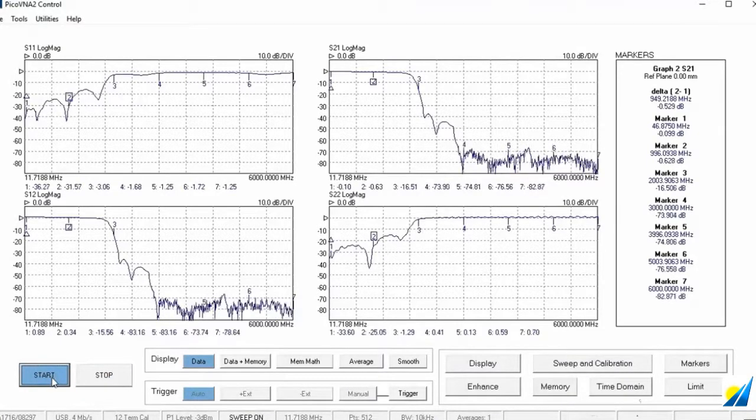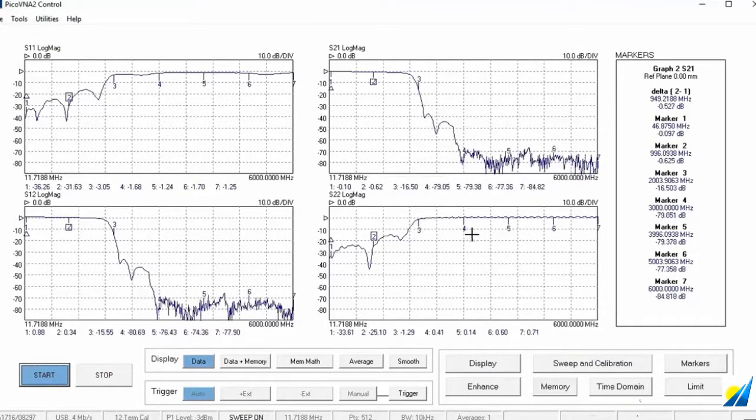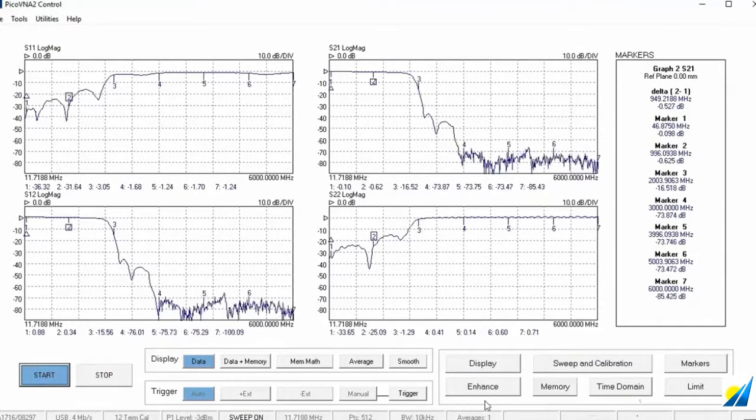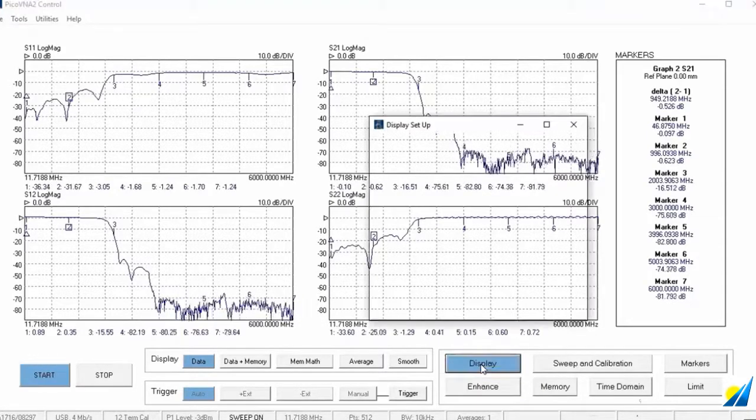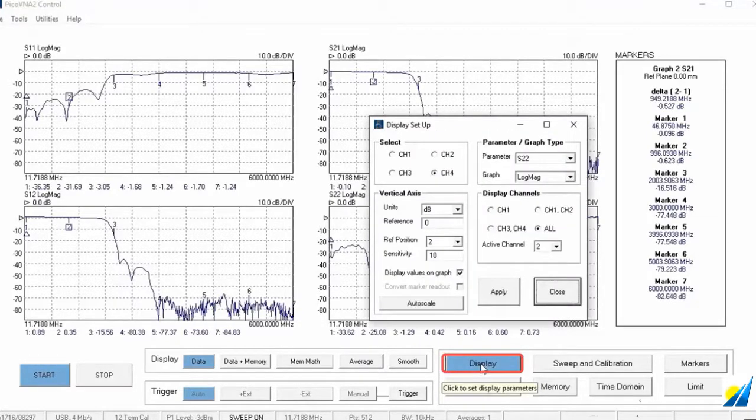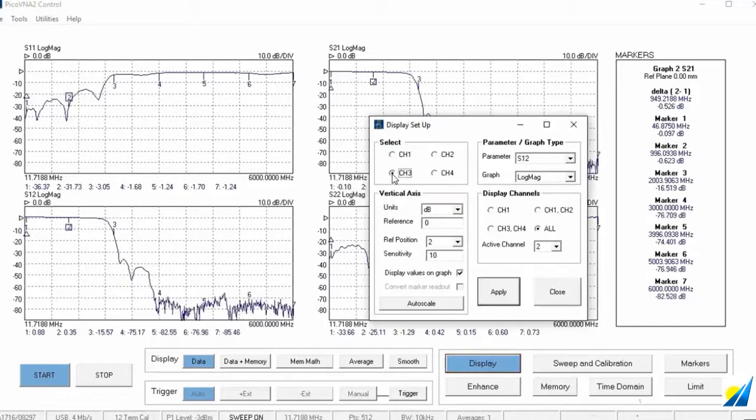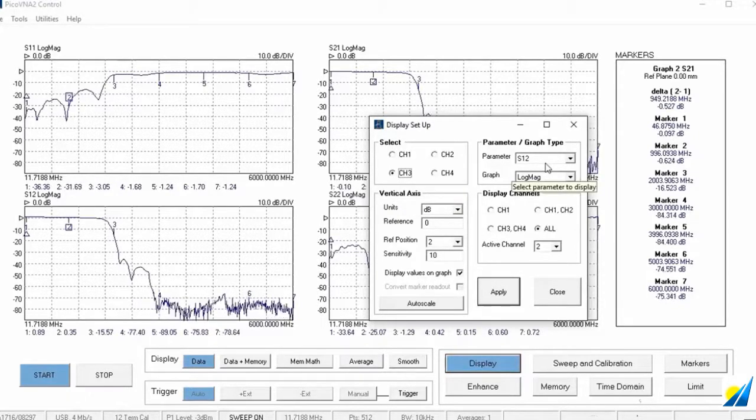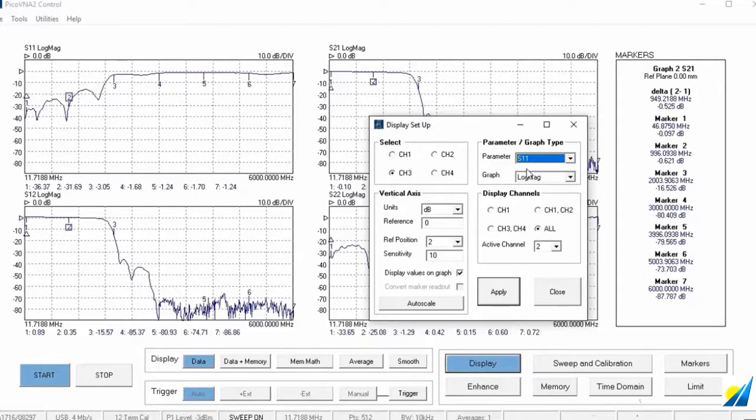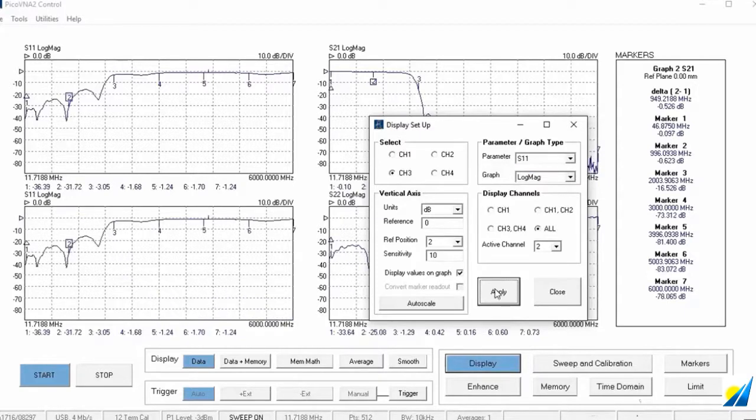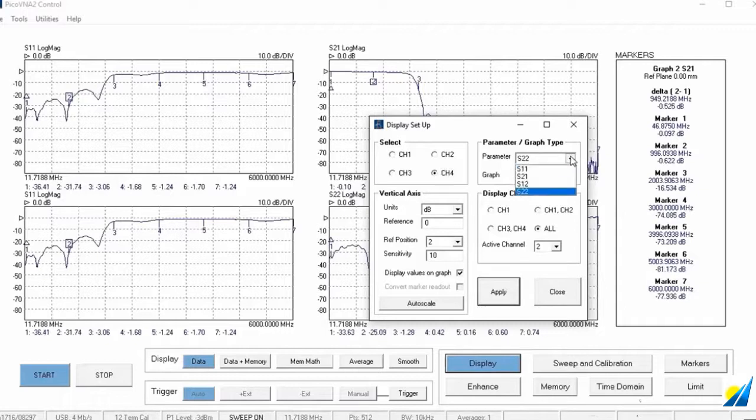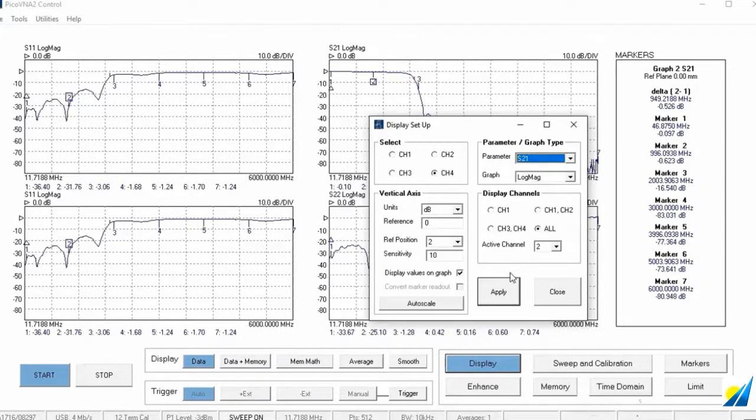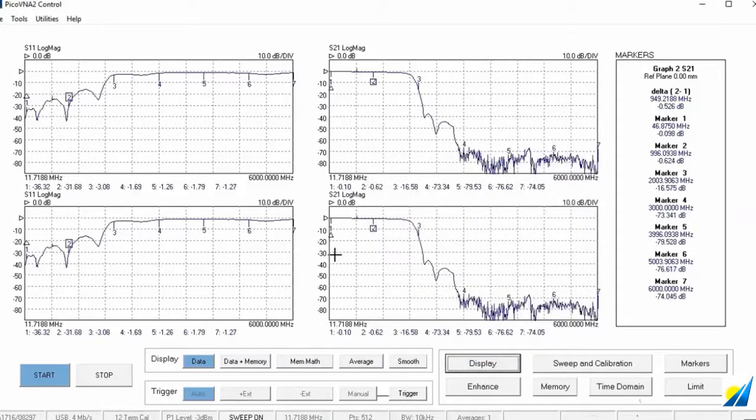Let's get that started and we'll move to some other flexibilities of our display here. So in the display menu, let's move down to channel three. It's currently showing S12. Let's put that over to S11 and let's go to channel four and let's put that over to S21 and close that menu.